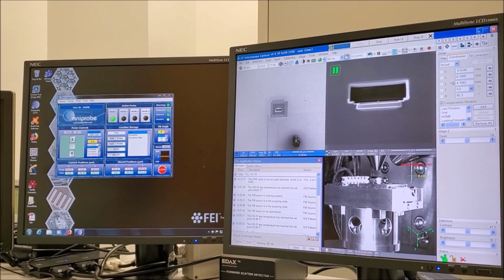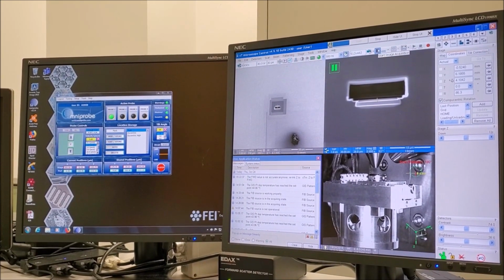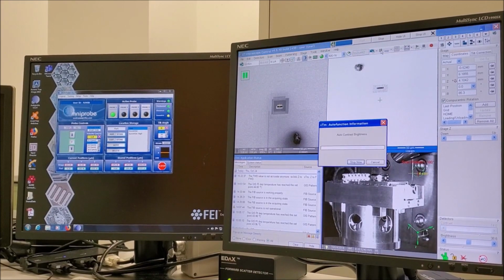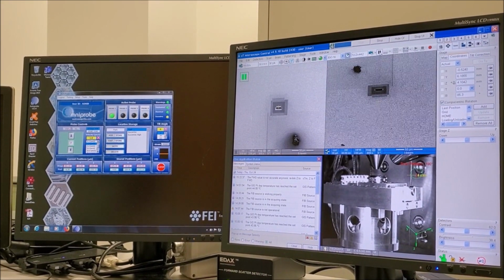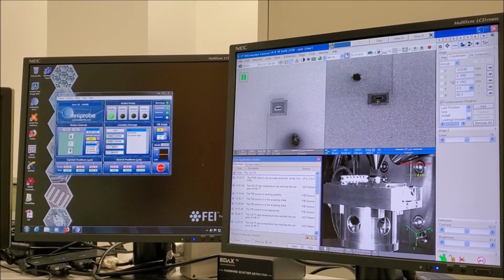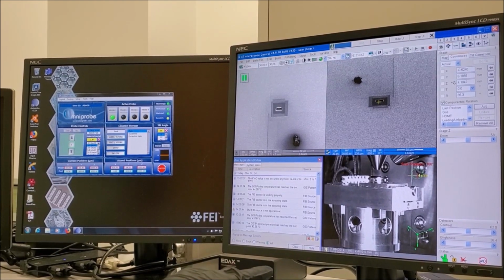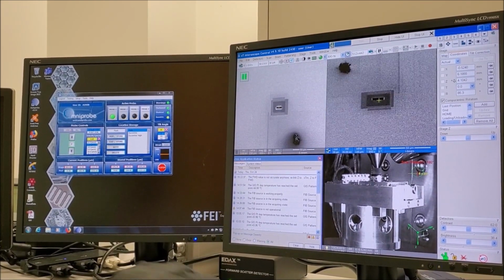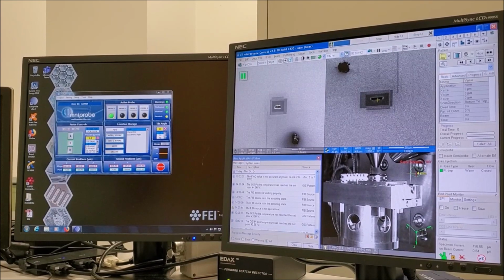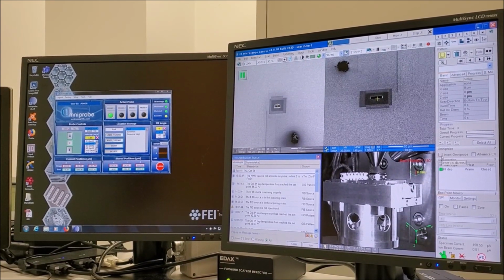When the stage tilt has returned to 0, activate the ion beam quad and reduce the current to something in the tens of picoamp range. Then unpause the ion beam quad and use the shift knobs on the manual user interface to adjust so the ion beam image is coincident with the electron beam image.